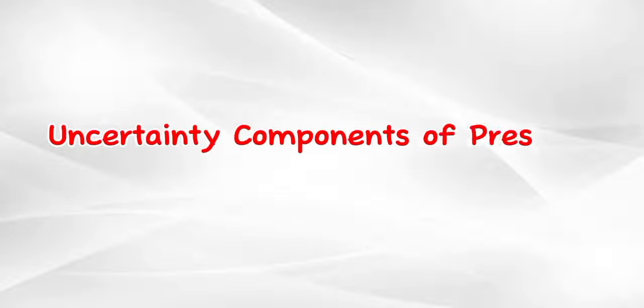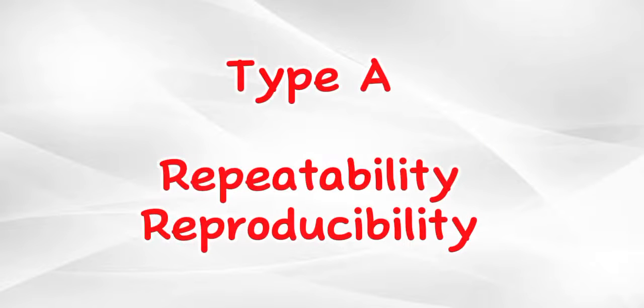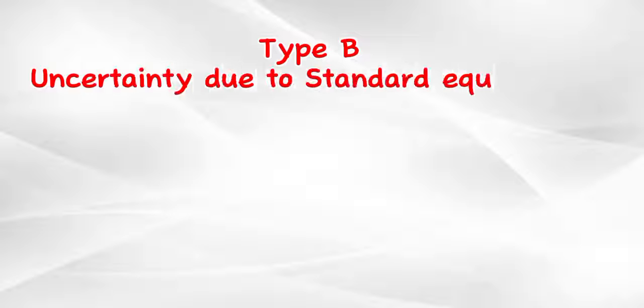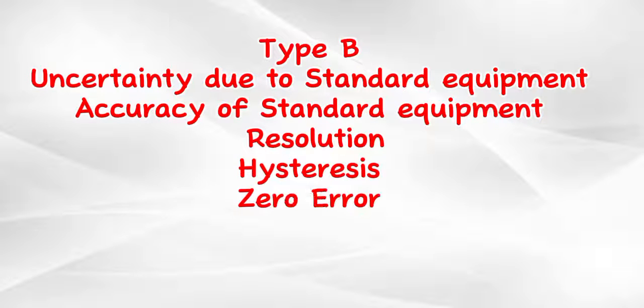Uncertainty components of pressure calibration to be considered, but not limited to: Type A - Repeatability; Type B - Uncertainty due to Standard Equipment, Accuracy of Standard Equipment, Resolution, Hysteresis error.